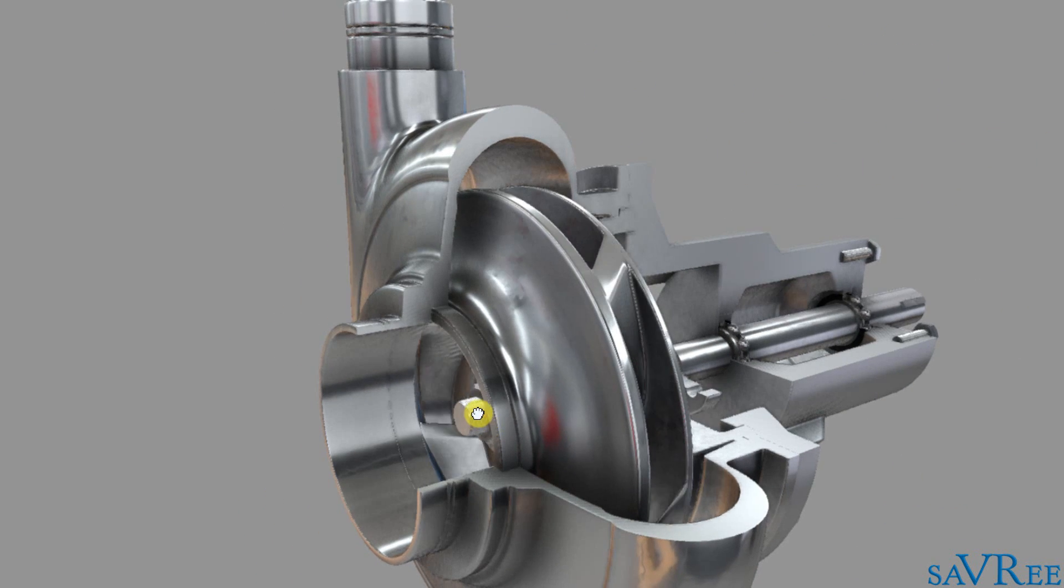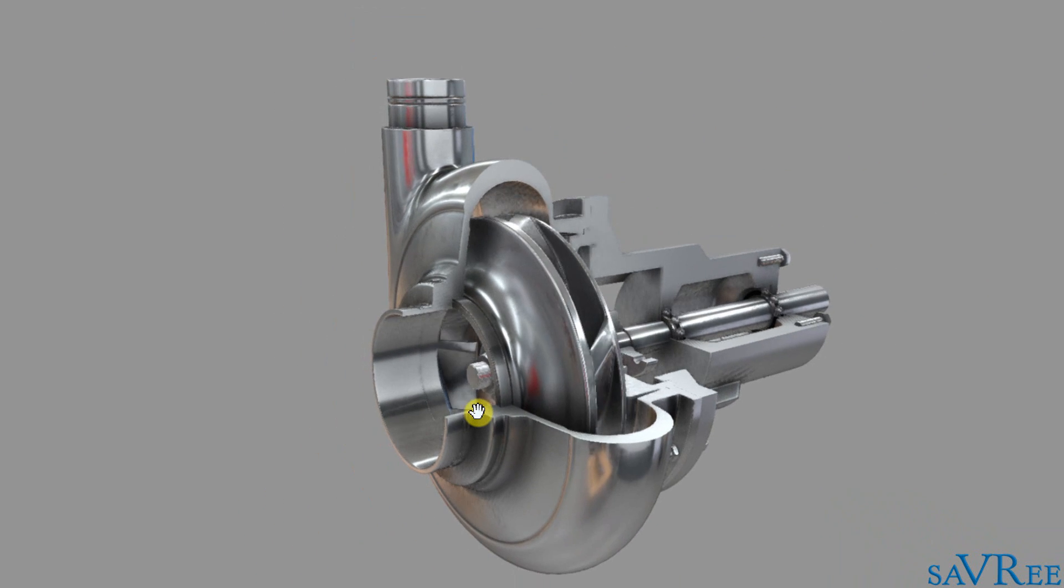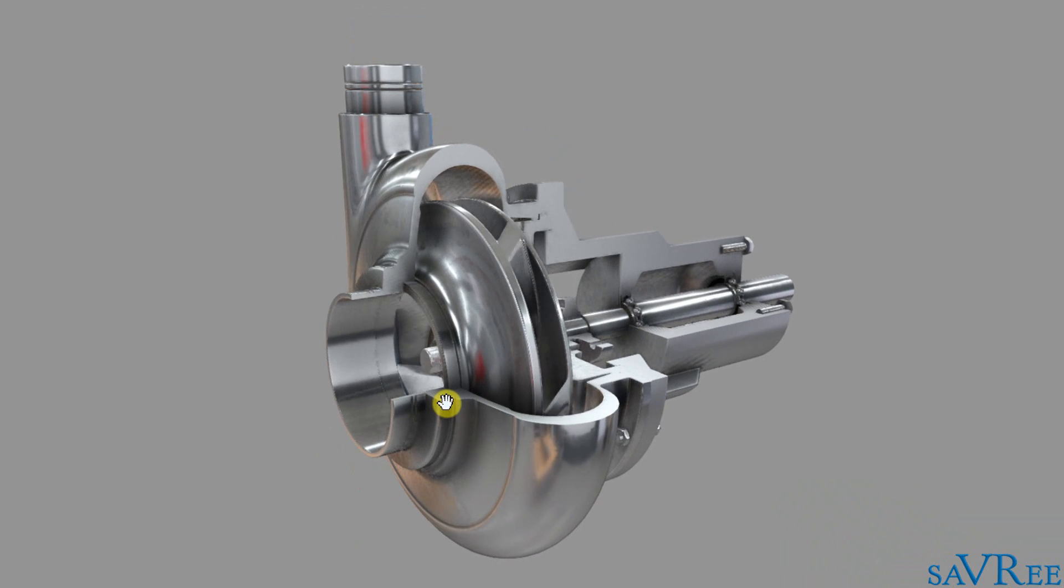So how is it that the centrifugal pump works? You can see from the design and the animation that the pump's construction is quite simple. Essentially, we've got an impeller rotating within a volute casing. And as it rotates through the liquid, we're creating pressure. And this pressure differential, that is the difference between the suction side of the pump and the discharge side of the pump, is what causes the liquid to flow.